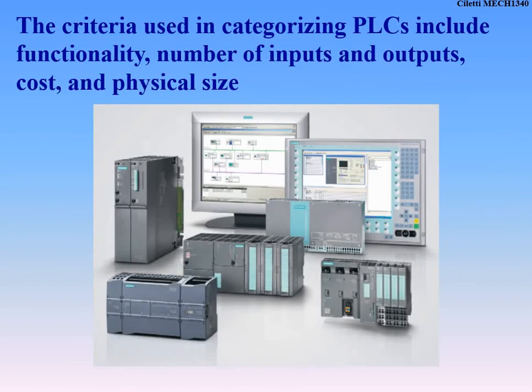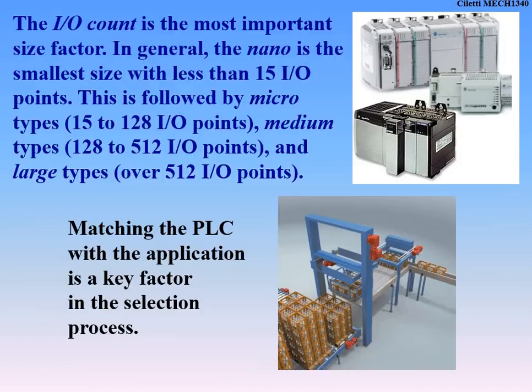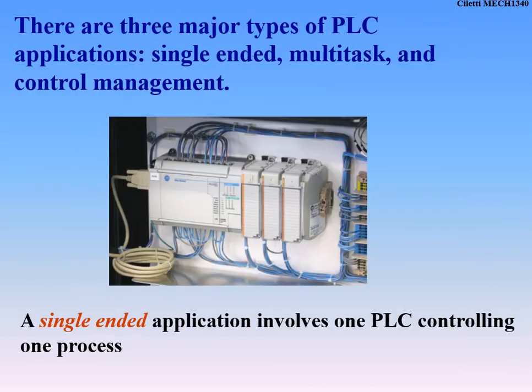PLC size and application really depends on what you're running and how many inputs and outputs you need. Small PLCs have anywhere from 15 to 128 IO. Medium ones handle 128 to 512 IO. Anything large is over 512 inputs and outputs — that's a pretty large PLC doing a lot of different things, and it might be your master PLC overseeing all the others. The three major types are single-ended, multitask, and control management.